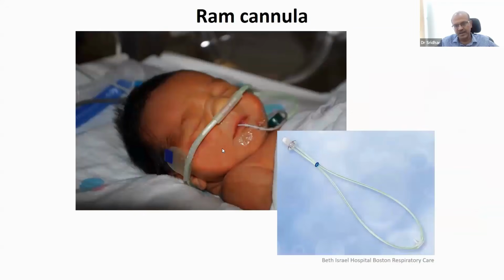And many of you may be using RAM cannula. There is controversy around RAM cannula because of the variable level of pressure delivery. So this is a single cannula. It's a closed loop, so you need the leak around the nostrils, 30% leak, to allow exhalation. Otherwise, the baby needs to open the mouth to exhale. That's not always ideal. And this adapter fits all ventilator connections, similar to the ET tube adapter fitting to the ventilator Y-piece. So we have different sizes of this, and you can use the right size, which gives you the 30% leak, and it's fairly simple to secure around the baby, and it stays quite well. We can put tape around this part to secure it.